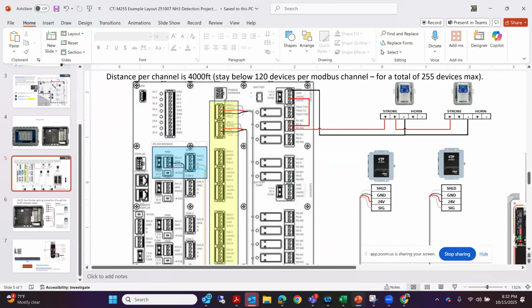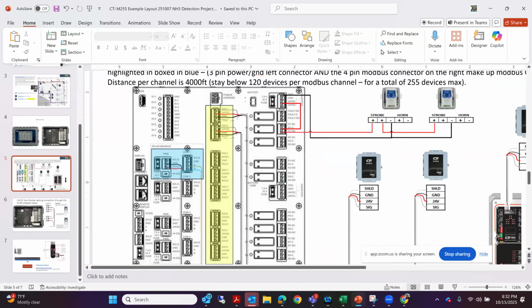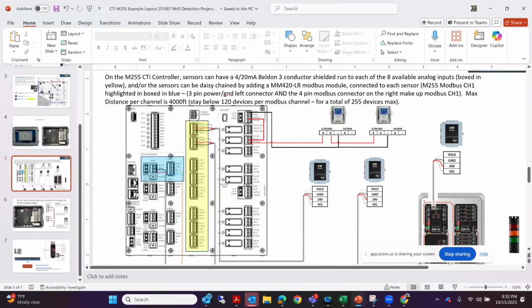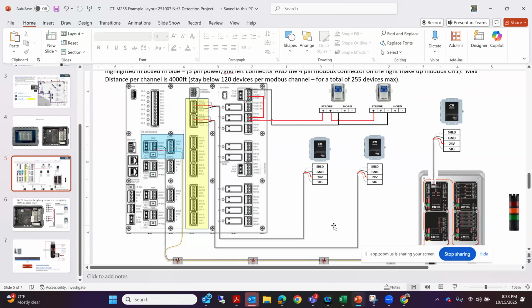You can connect it to the internet right here. And as long as you're connected to the internet, you are going to be able to see all those values, the values of those registers that's capturing that sensor concentration in parts per million, and it's capturing all these relays. So when you turn on coolers 1 and 2 horn strobes, you know that that zone of horn strobes has been turned on without having to make any connections because you're already on the network. So the refrigeration controls can see this, and it's nice to be able to have that, so you can get that data over to them as well if they're doing anything special with the refrigeration controls output relays.